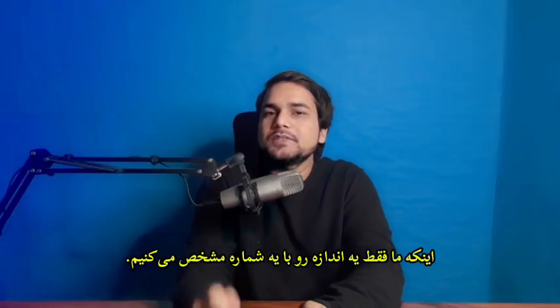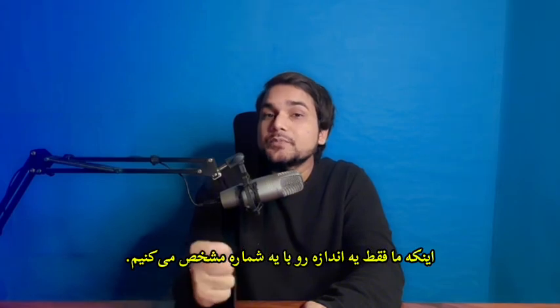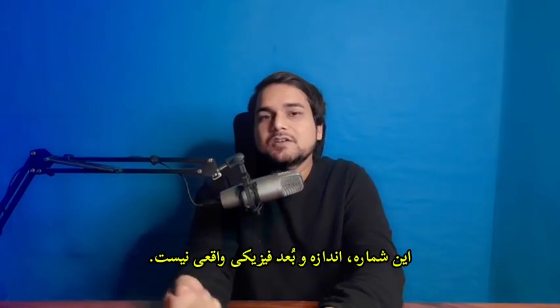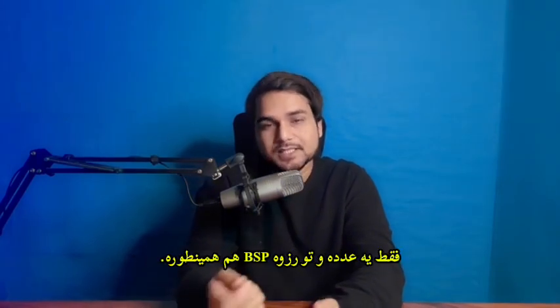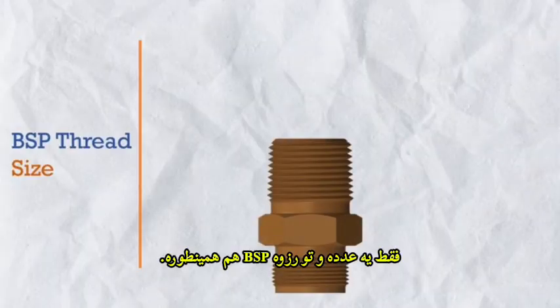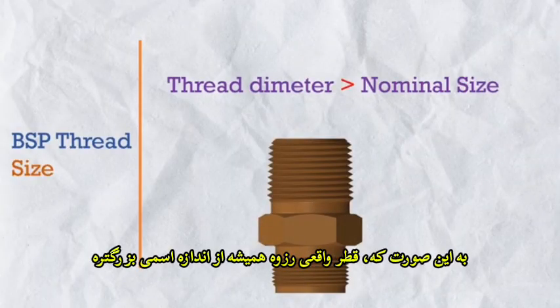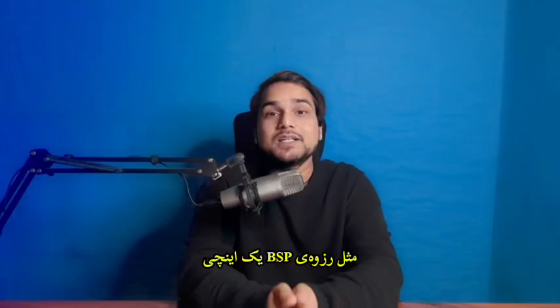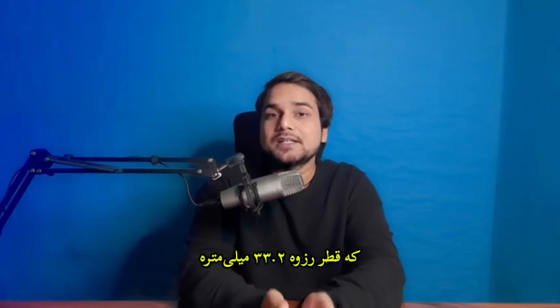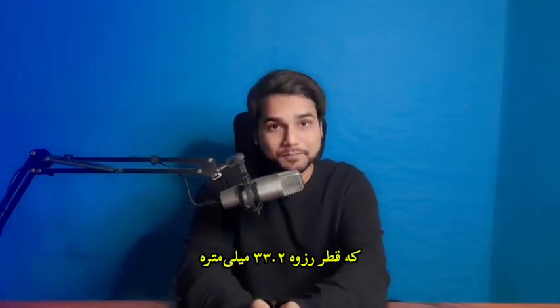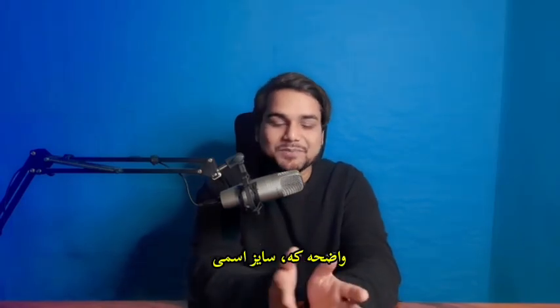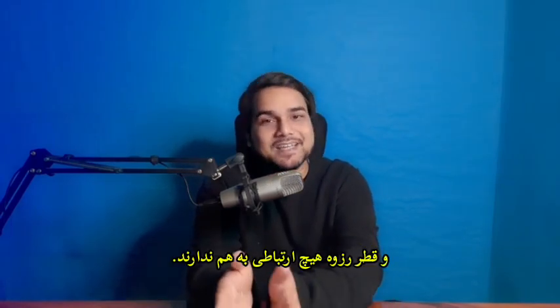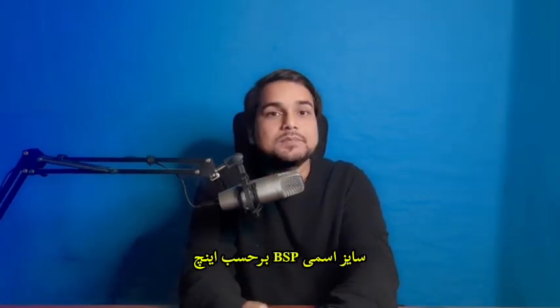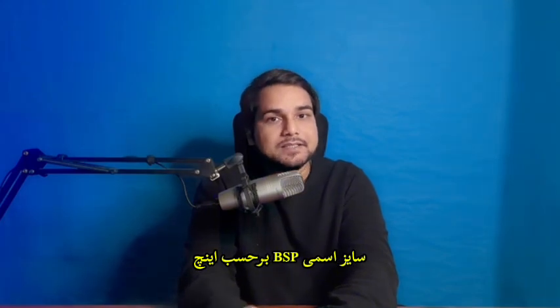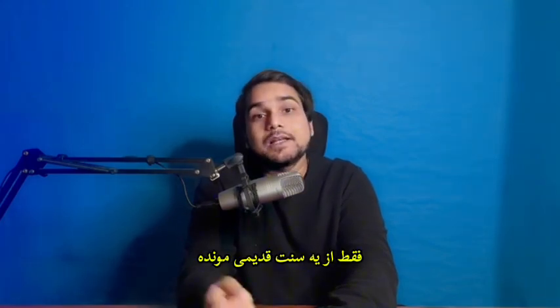So this 1 inch is just a nominal size. Nominal size means we just denote some sizes by some number. It's not the physical dimension. It's just a number. And in BSP thread, the thread diameter is always larger than the nominal size, like in 1 inch BSP the thread diameter is 33.2 mm. There is no relation between nominal size and the diameter of the thread. The BSP nominal size in inches just comes from historical legacy.